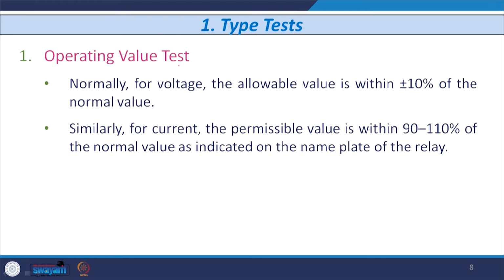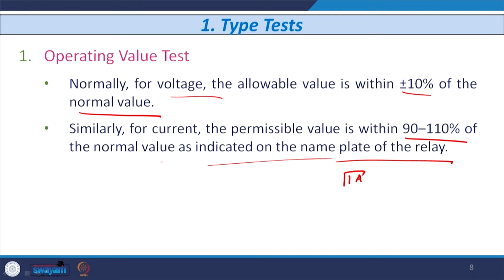Now, when we consider the operating value test, there must be some limit for each and every quantity. If I consider voltage, the allowable value is within plus or minus 10% of the normal value, and if I consider current, the permissible value is 90 to 110% of the normal value as indicated on the nameplate of the relay. If I use a current relay, then on the nameplate the reference normal value is indicated, and when you use a voltage relay, the nominal value is also indicated on the nameplate. So, the variation allowed in voltage is plus or minus 10%, and in current it is 90 to 110%. If 1 ampere, let us say, is the nominal value in case of an over current relay, then the allowed variation in this current is 0.9 to 1.1. So your reading should fall within this band.